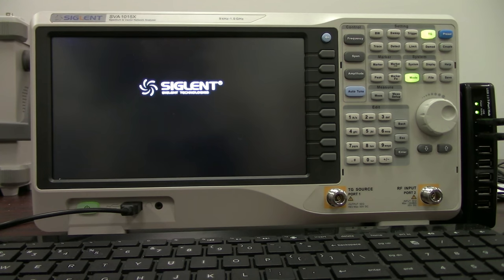Again, if you can't get to the instrument, it will automatically boot up and start operating again. And with the new web server that we have inside the instrument, you can then go into the instrument via web browser remotely.